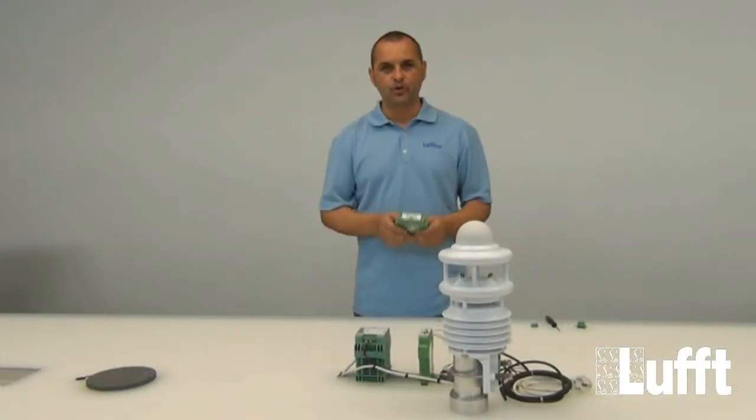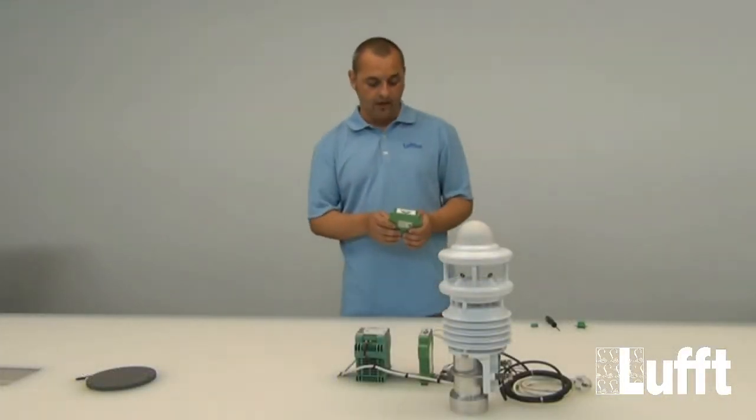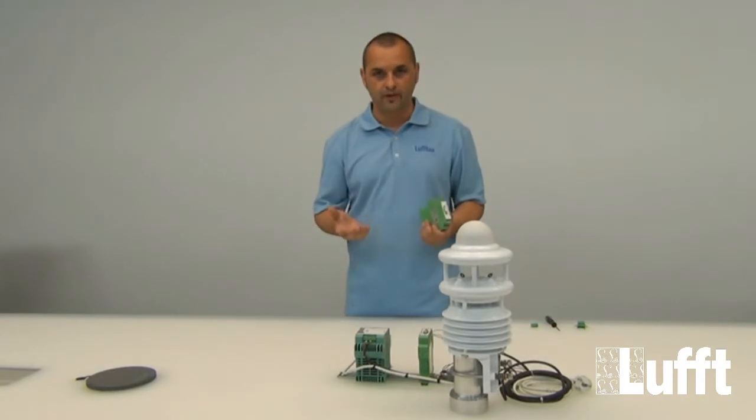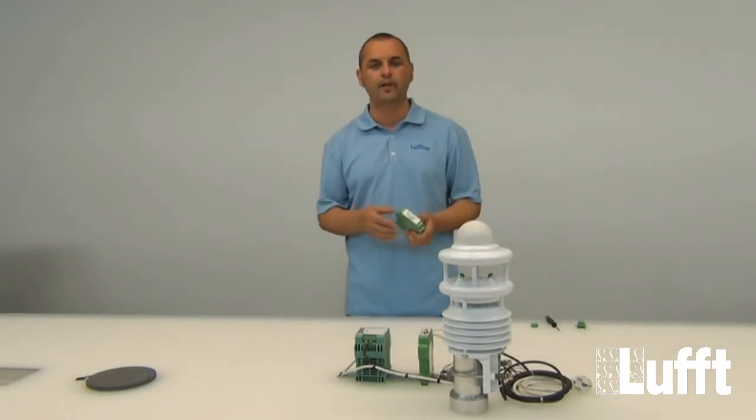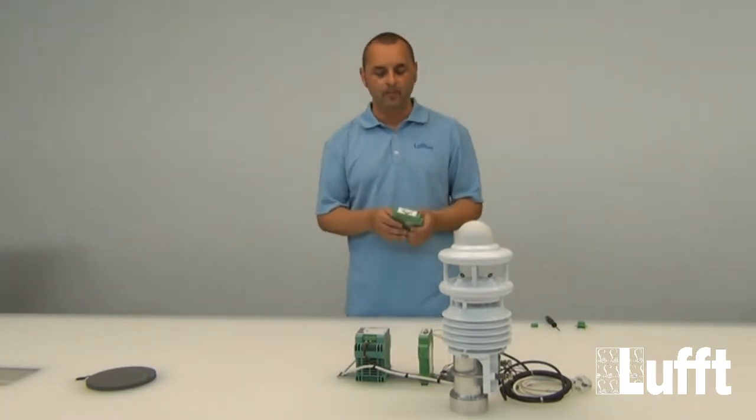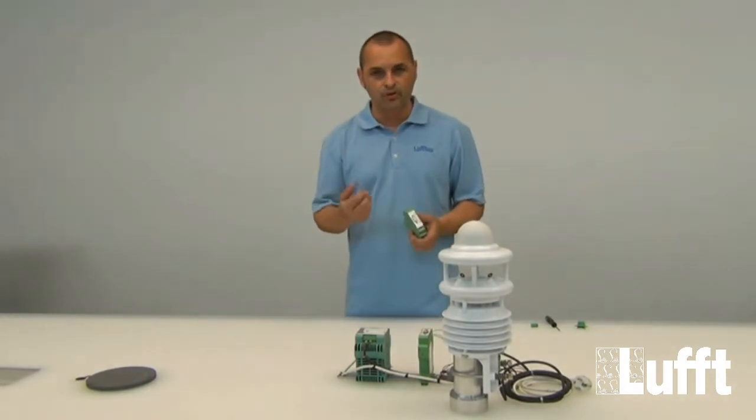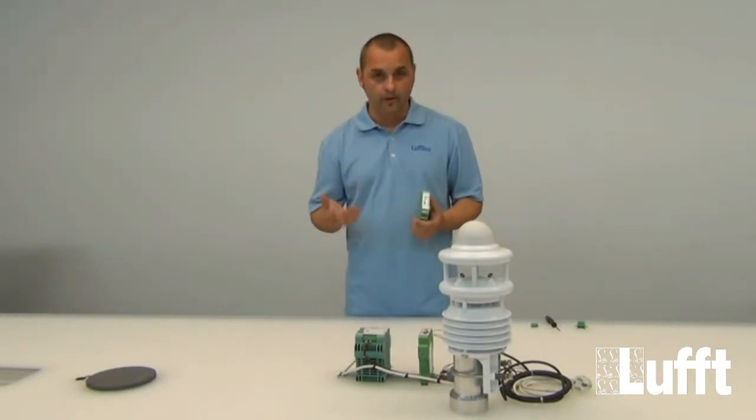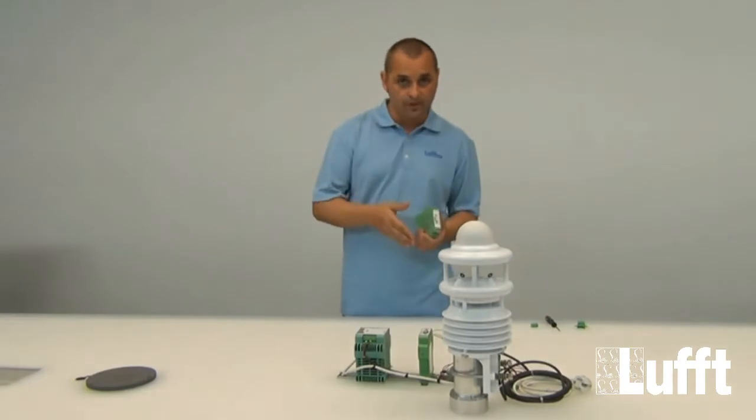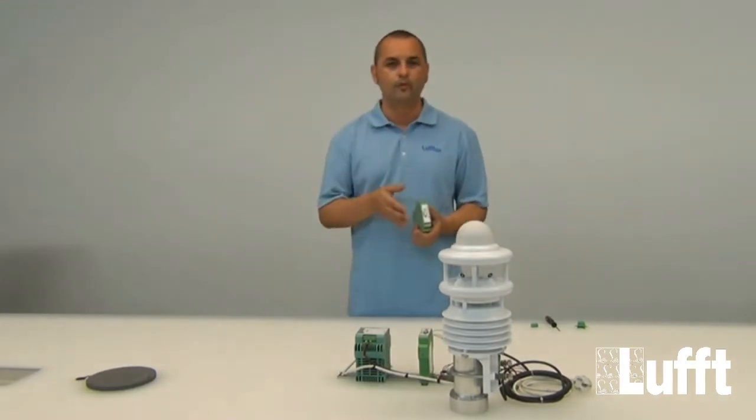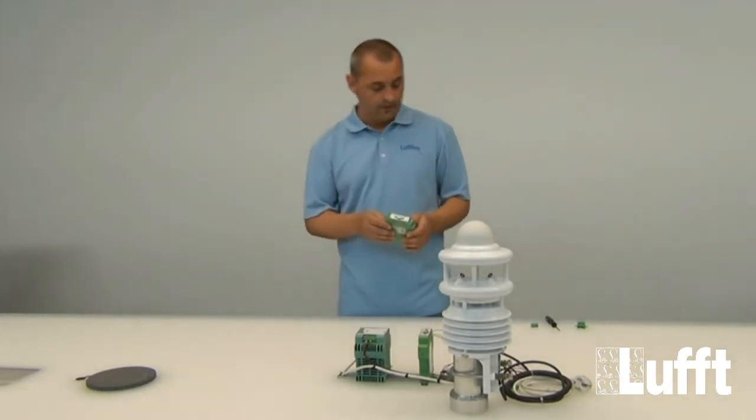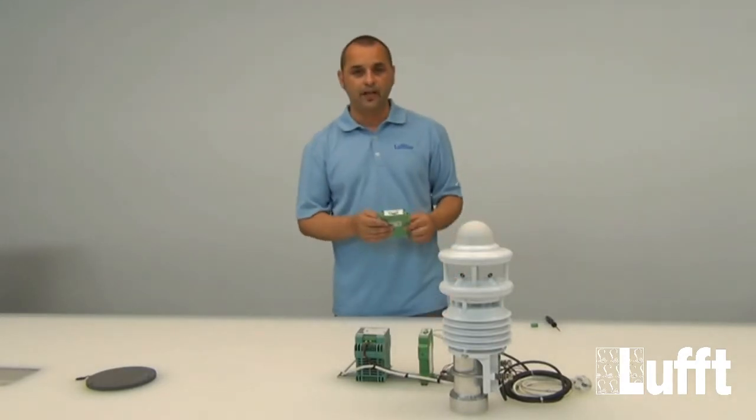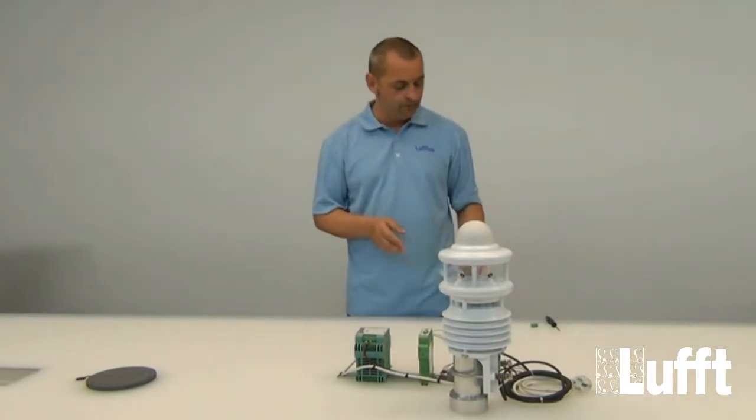The signals which you can produce are first current signals, for example 0 to 20 mA or 4 to 20 mA, and you can also choose for voltage between 0 and 10 volts or 2 and 10 volts.